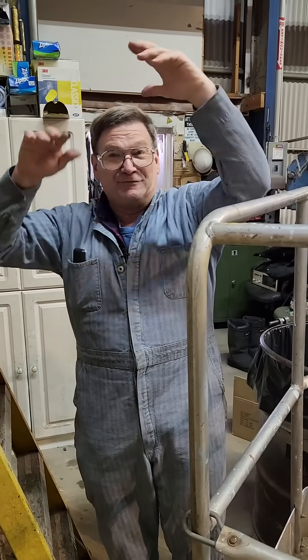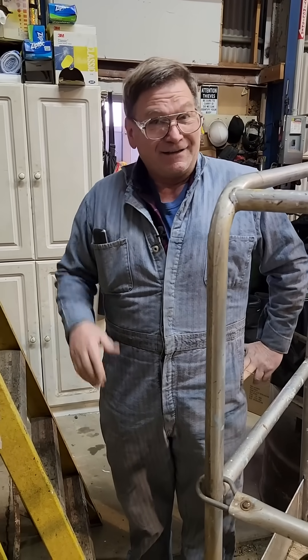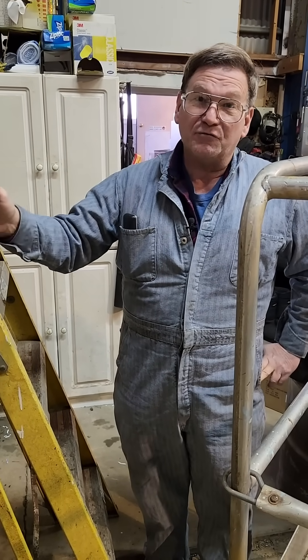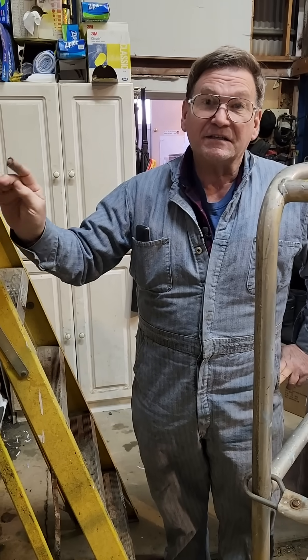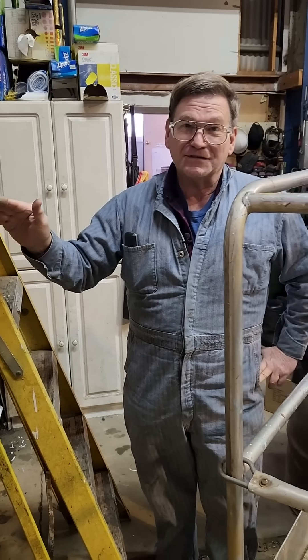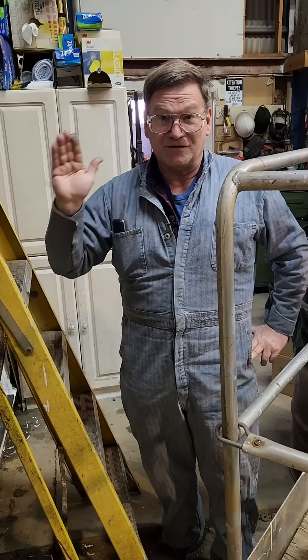The door tried traveling open to infinity when I did that one day — bent the little stop bolts, crooked the whole thing, and it was 20 below. It was way worse than what happened today. So on single-phase motors, when you're reversing direction, let it stop first. Trying to do a quick reverse, sometimes you're going to get in trouble and it's not going to reverse — it's going to go to infinity.